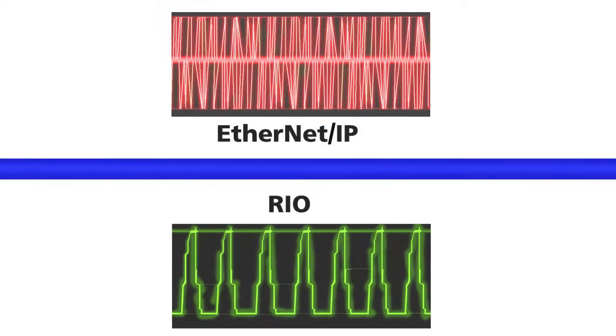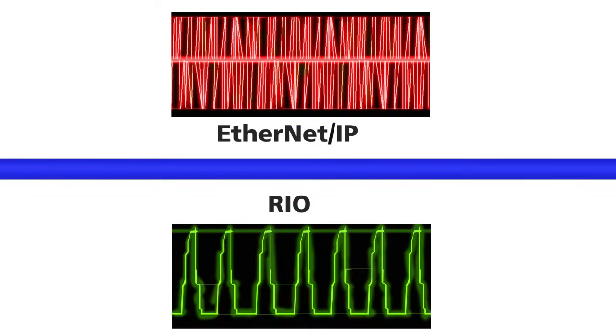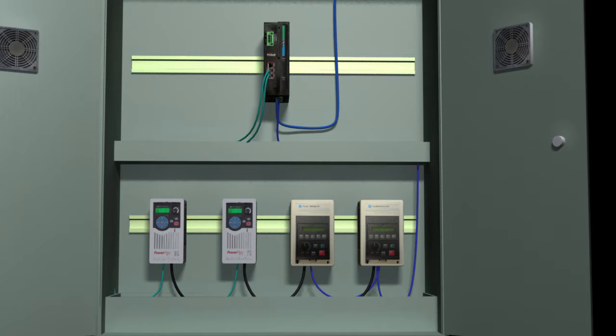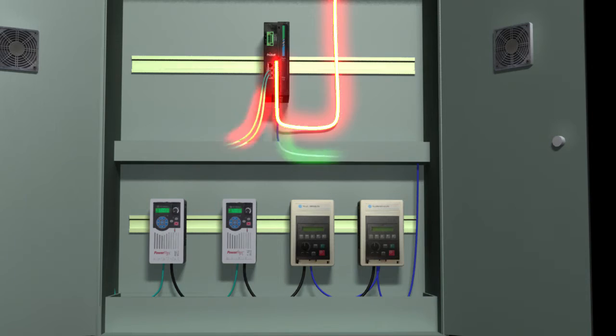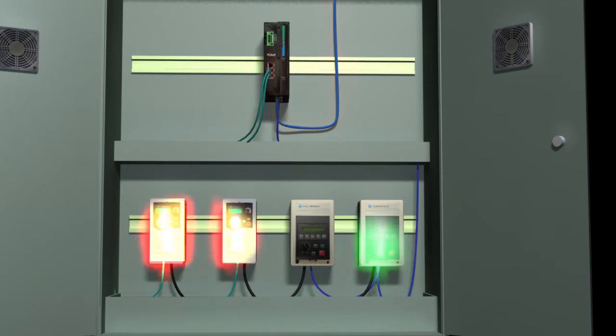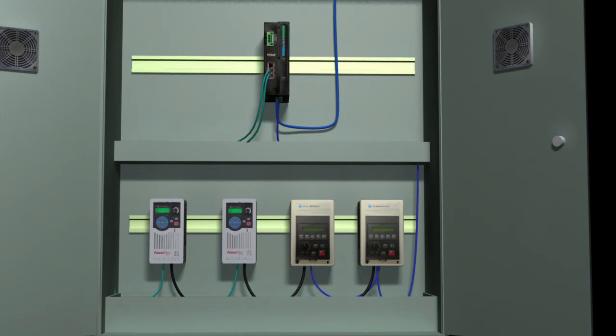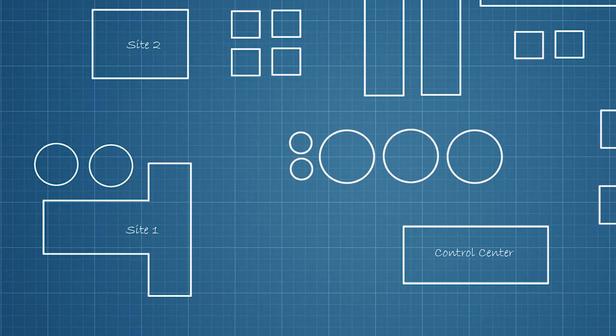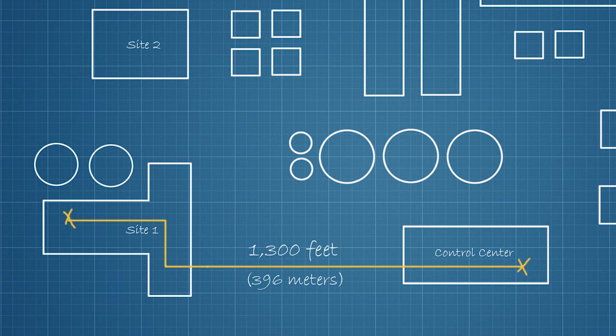These two signals are combined into a complex waveform in the media converter, and then sent out through the trunk connection on the new trunk line. There can be up to 1300 feet between drops without a repeater.